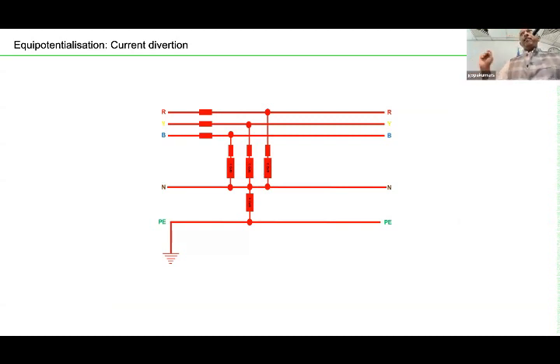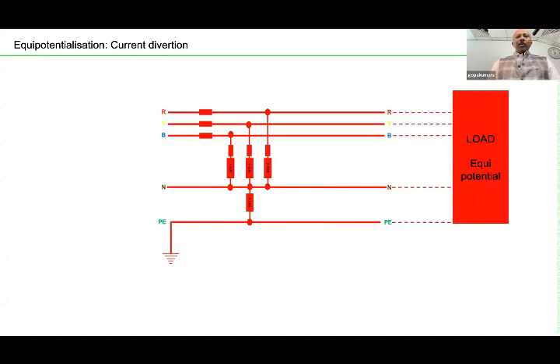Now, look at the picture. At the main distribution board, you have an SPD, and the SPD has made an equipotential bonding. Now, if the distance from the location where the SPD is installed to the internal system, the line length of all the 5 wires, is almost equal, then the equipment will not experience a surge.